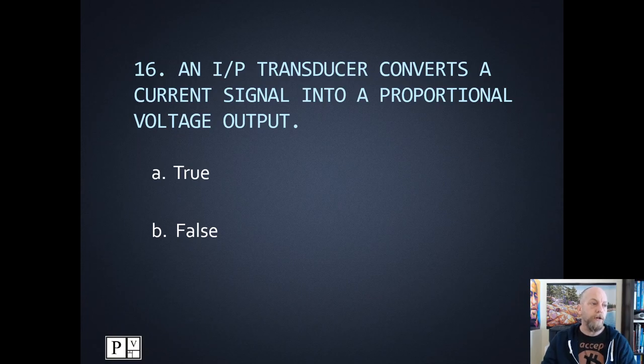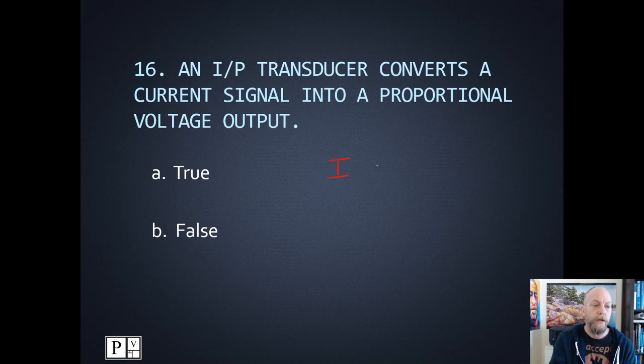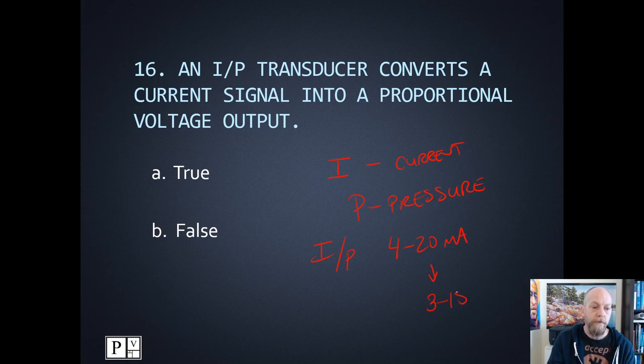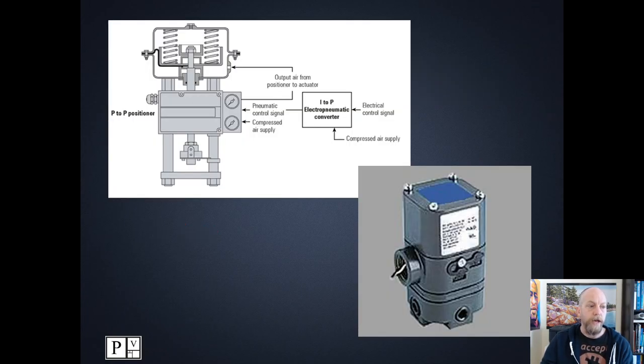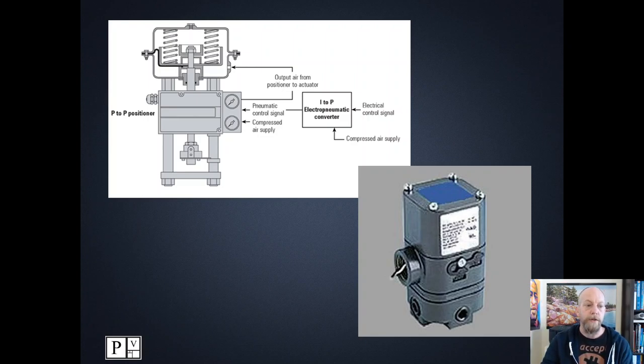Number sixteen: an I to P transducer converts a current signal into a proportional voltage output. I is for current, P is for pressure. This current to pressure transducer takes the standard 4 to 20 milliamp current and changes it to a 3 to 15 psi pressure — nothing there mentions voltage. Number sixteen is false. The current to pressure transducer was mounted on the side of a larger valve — current goes in, modulating 3 to 15 psi onto the top of the valve, pushing down on the diaphragm and spring to open and close the valve. Think of the I to P transducer as a variable solenoid.